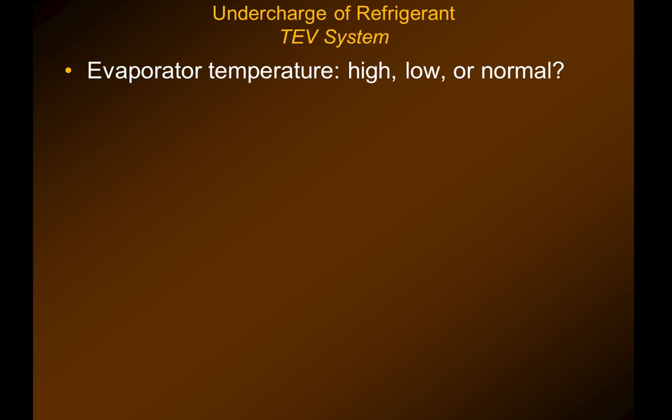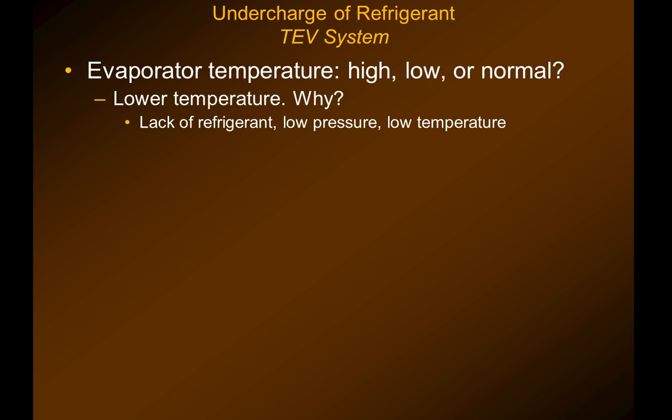So the evaporator temperature — is it going to be high, low, or normal? It's going to have a lower than normal evaporator temperature. That's due to the lack of refrigerant, which causes low pressure. And because of the temperature-pressure relationship, there is also going to be a lower temperature in the evaporator coil. That's why in residential air conditioning, sometimes you see the coil freezing when there's an undercharge.